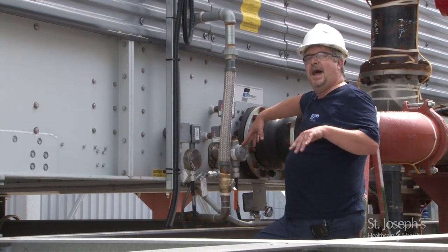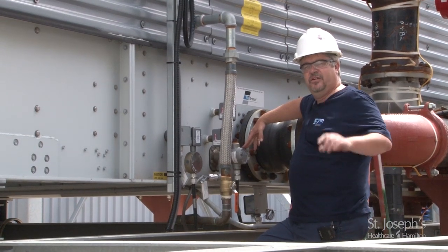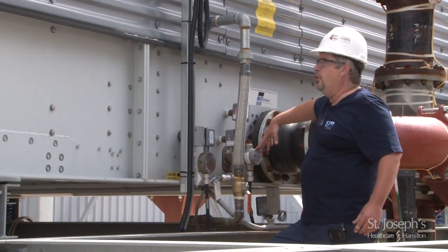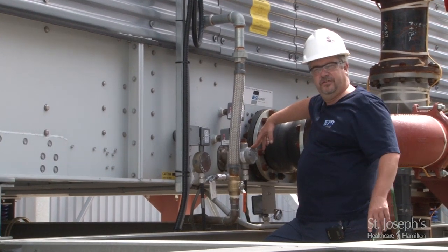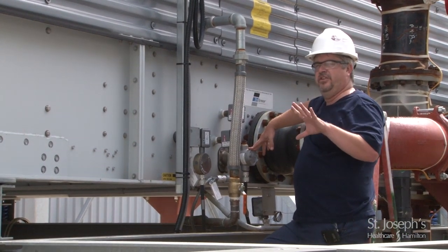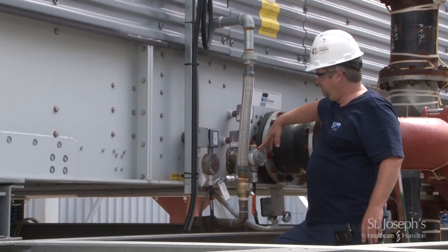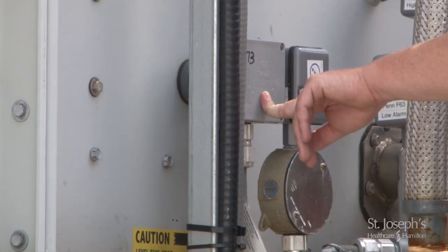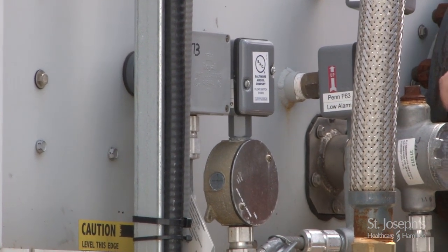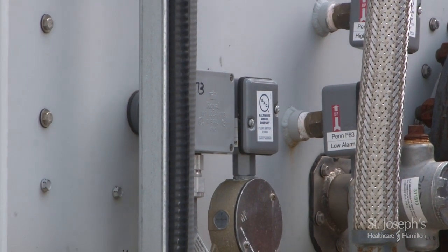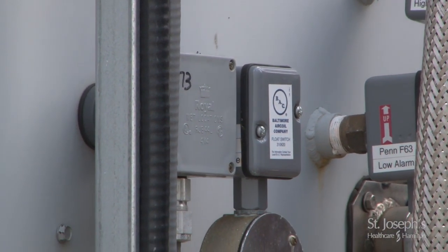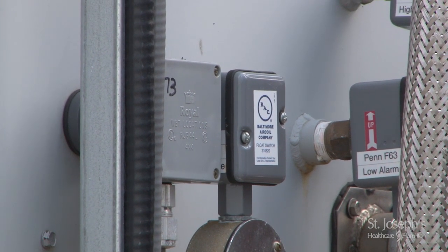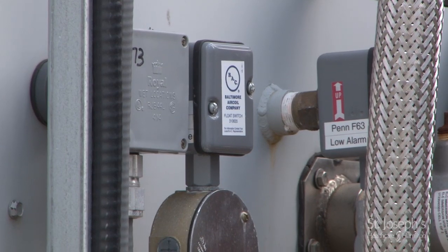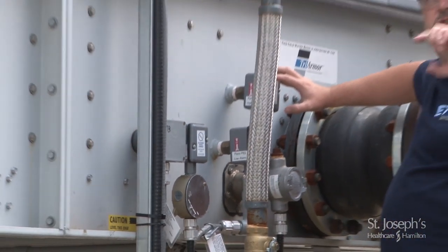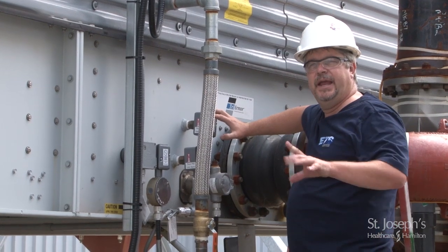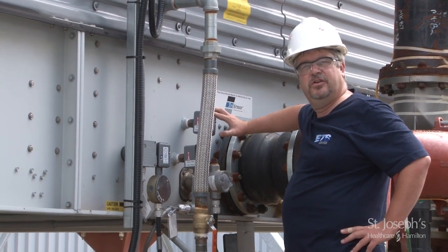When it goes offline, as the building load is not near as high as it would be in summer operation, there will be a lot of times where the fans aren't running, the water isn't flowing, and this unit's just sitting with water within the basin. The last item on here that we didn't see in the summer tower is this gray box. Inside that gray box, if we were to open it up, is the thermostat. That thermostat just monitors the temperature of the water within the basin and keeps it at a 45-degree Fahrenheit temperature, which is just slightly above the freezing mark. And again, that's solely to protect the basin from freezing during winter operation.